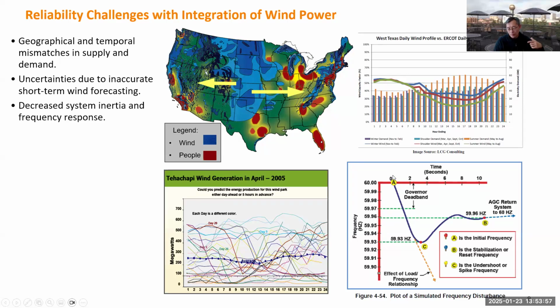After a disturbance, the system frequency will go through three stages. First it will decline at a certain speed. This speed only depends on system inertia. So if the system inertia is large, this slope will become very shallow, much smaller.